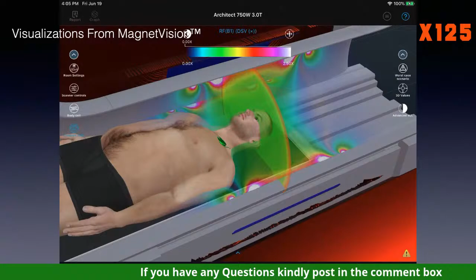So in summary, with respect to the information you get from your MR system manufacturer, when it comes to the static magnetic field, both in terms of the field strength and the spatial gradient information, in my opinion, the manufacturers do a very good job of getting us appropriate information for static field. For the time-varying gradients, they do a decent job. I would like to see more detailed information, but that information is generally pretty useful.